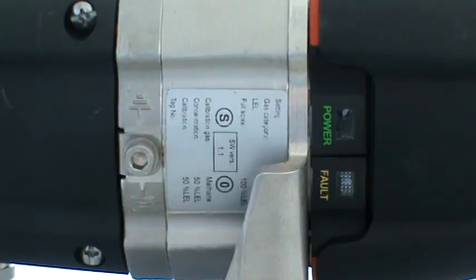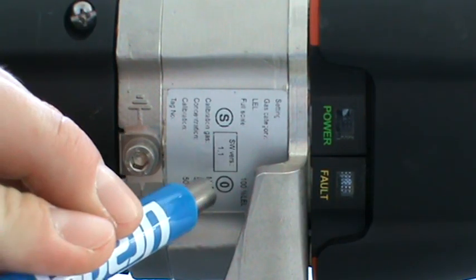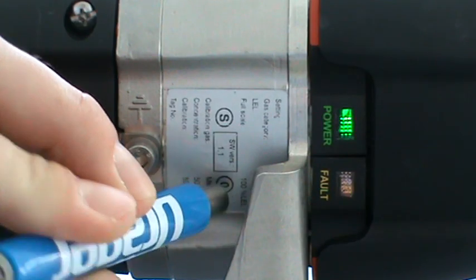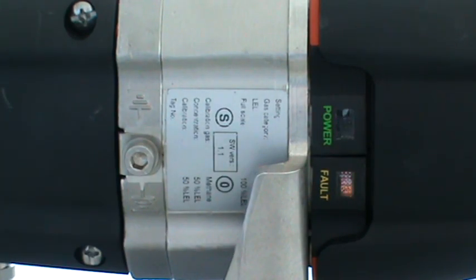But if you want to perform a real adjustment of the PIR 7000's measurement to a proper 0 point, which is your second option, then you should place the magnetic wand again, now for the 4th and last time, on the 0 sign of the configuration label. Now the 0 point is adjusted to a proper 0, whatever it was before. And after some seconds of saving these data and doing some software checks, you see that the instrument switches back to normal operation, to normal measuring mode. The green status light is on.